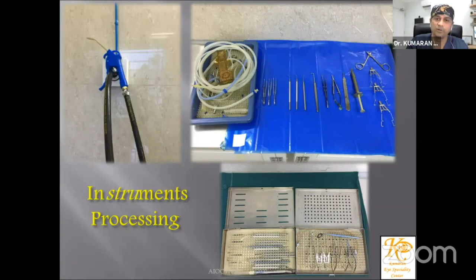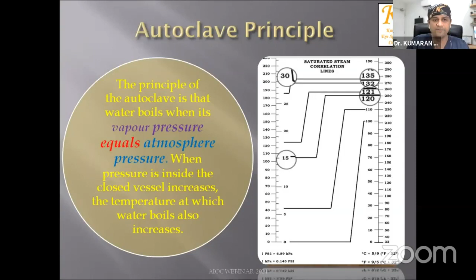Packing should be done in any of 3 forms: with linen, paper plastic pouches, or non-woven paper as per the GSM listed here. It is a good technique to place all the trays vertically as shown here so that there's steam penetration all around. The autoclave principle is common to everybody, as we know that water boils when the vapor pressure equals the atmospheric pressure.